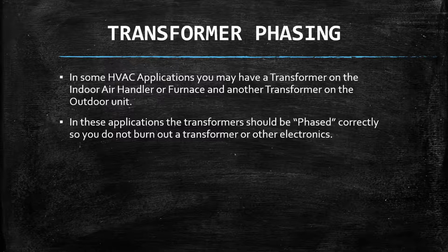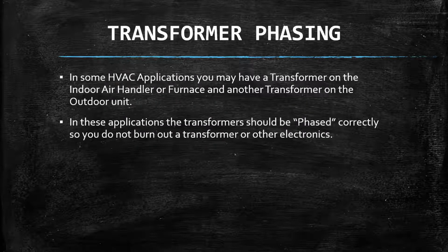In some HVAC applications, you may have a transformer on the indoor air handler or furnace and another transformer on the outdoor unit. In these applications, the transformers should be phased correctly so you do not burn out a transformer or other electronics.